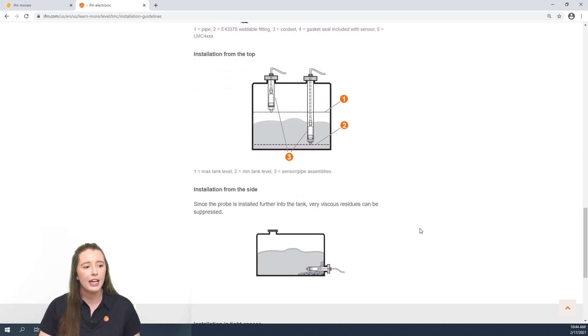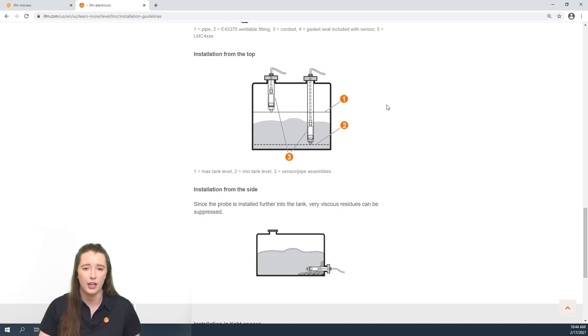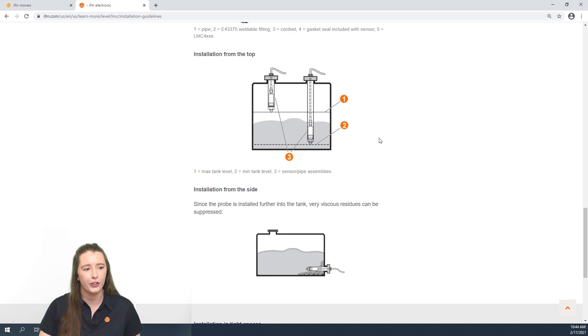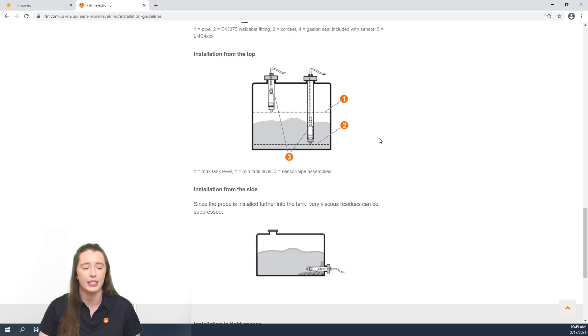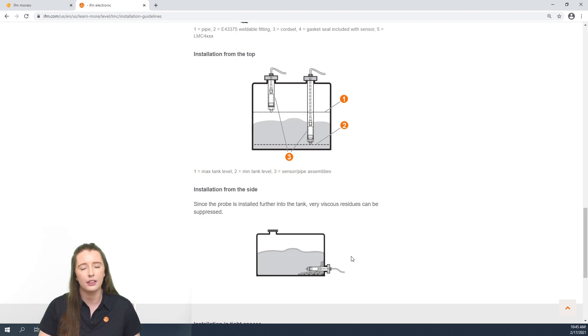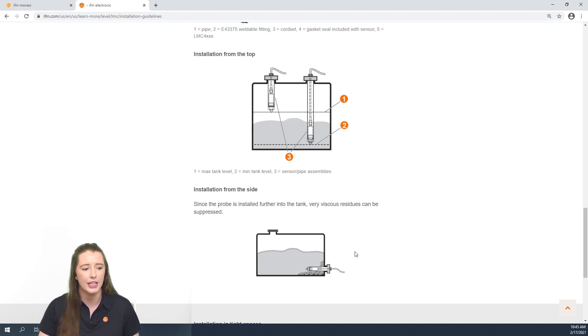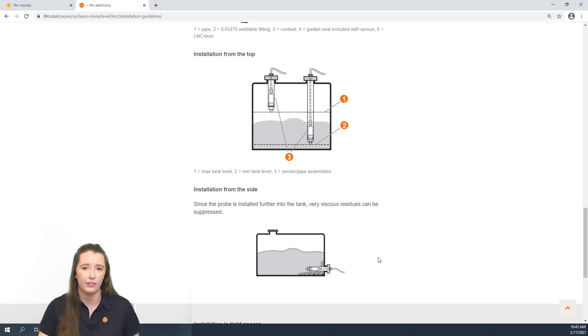Here we have images of how you can install these sensors from the top of the tank or from the side of the tank. In the first image they are utilizing two sensors to represent high and low level, and in the second one it allows you to extend the sensor further into the side of the tank to avoid any residue buildup in the corner of the tank.